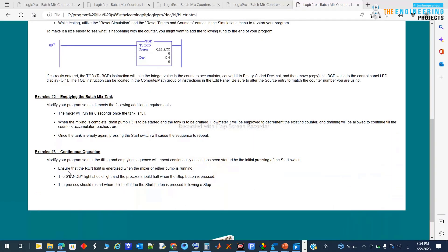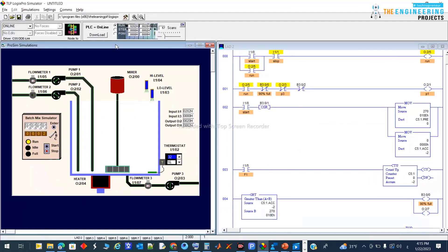The second requirement is to ensure the run light is energized whenever the mixer or either pump is running — which we will verify. Also, a standby light should illuminate and the process should stop when the stop button is pressed. Additionally, the process should restart from where it left off if the start button is pressed after a stop. Let's address these requirements now.